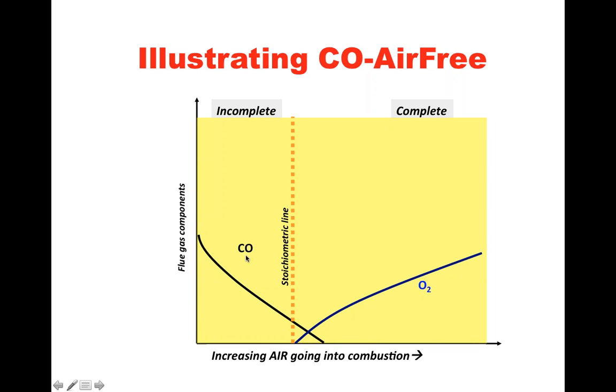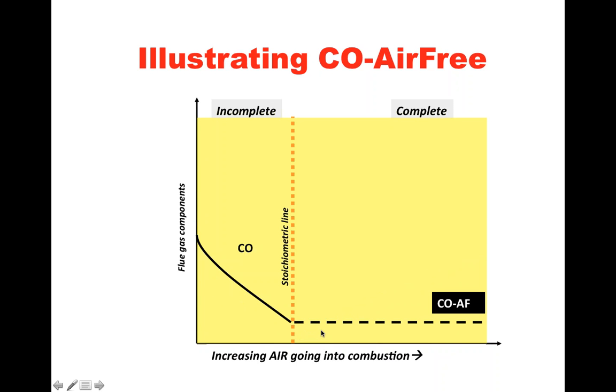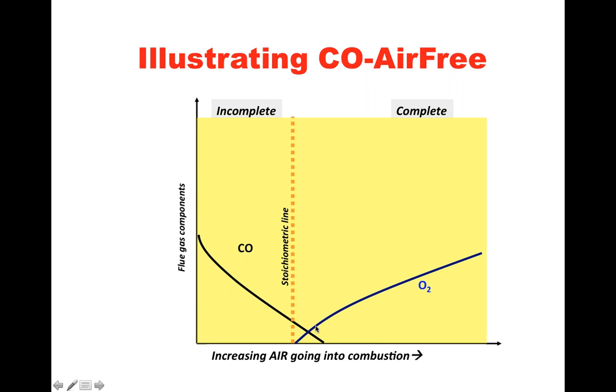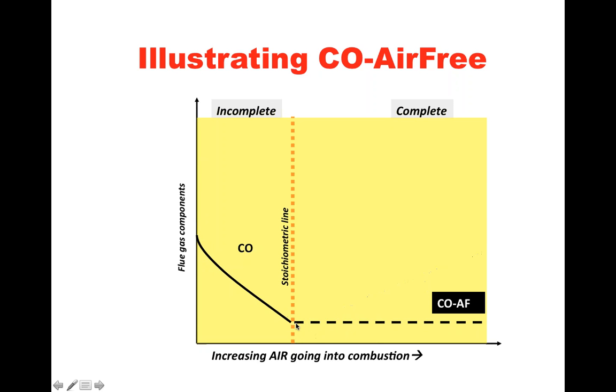The carbon monoxide level usually sharply declines as you move through incomplete combustion and through complete combustion, and because things are not always the same and there's a lot of randomness and chaos in combustion, you will get some CO levels diminishing as you go to higher levels of oxygen. But basically, CO is getting lower and lower as you move towards more air being introduced in combustion. The CO air-free calculation actually does a mixture between the CO level, we'll go back one slide, the CO level and the oxygen level, and we'll plot a line which is a pretty uniform or stable line of CO air-free. So it basically takes you back to the point where the carbon monoxide line crosses the stoichiometric line.